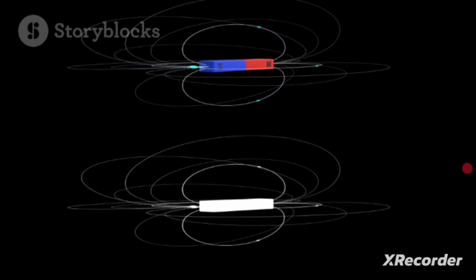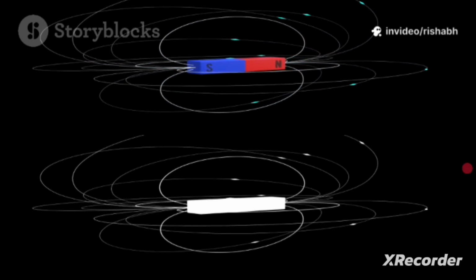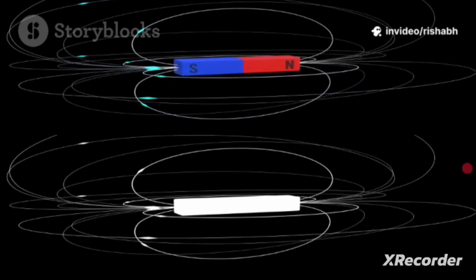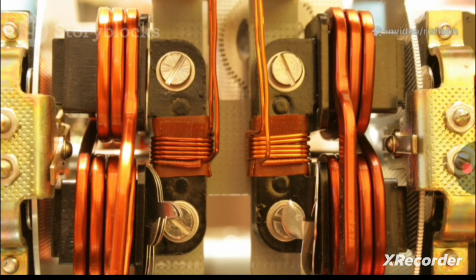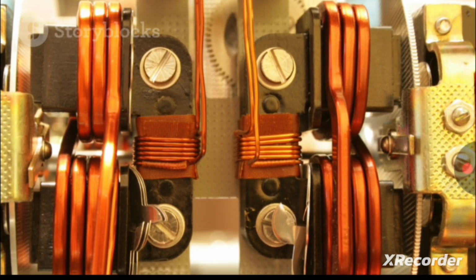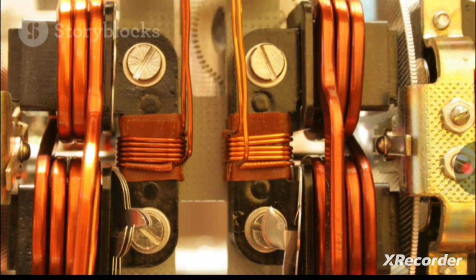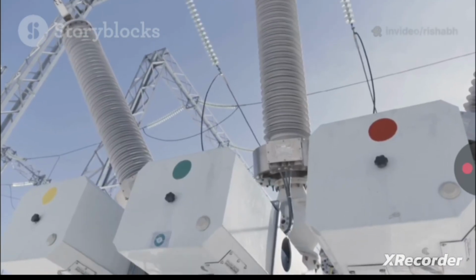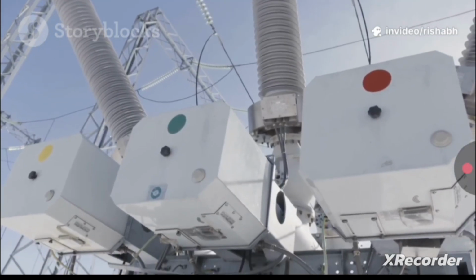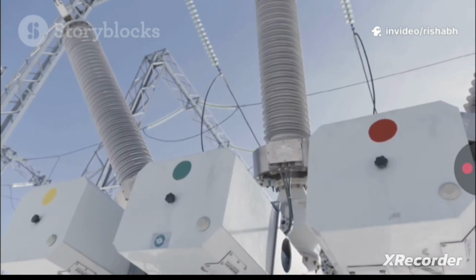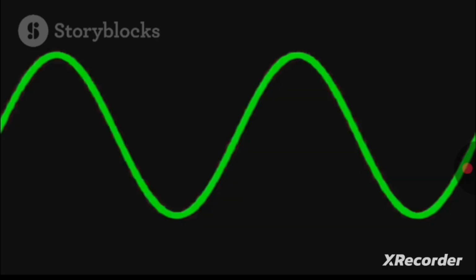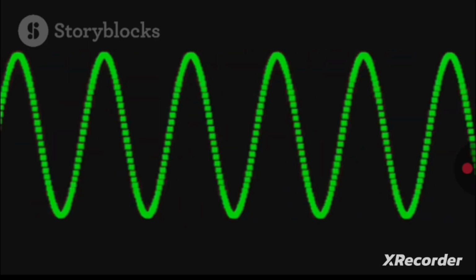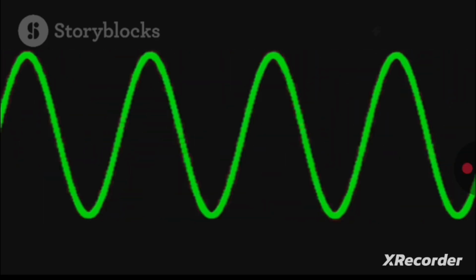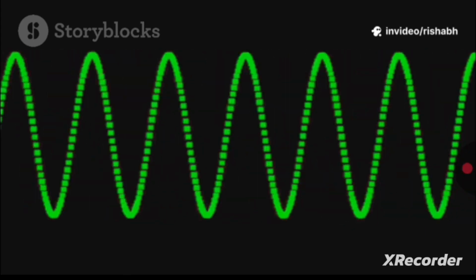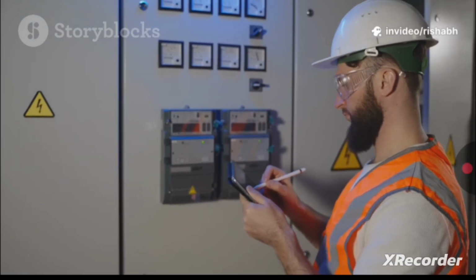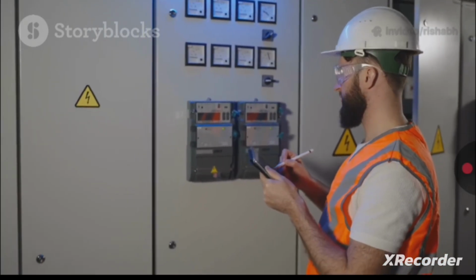This rogue flux creates a chaotic scene inside the transformer. Instead of smooth, orderly lines, the magnetic field becomes dense and distorted. The spilling flux induces unwanted currents, called eddy currents, in the metallic parts that aren't designed to handle them. This internal chaos doesn't stay quiet. The intense magnetic forces cause the transformer's core, laminations, and structural parts to physically vibrate. The gentle, steady hum of a normal transformer escalates into a loud, menacing growl or a deep, unsettling groaning sound. This audible noise is a clear distress signal that the transformer is operating under severe stress.